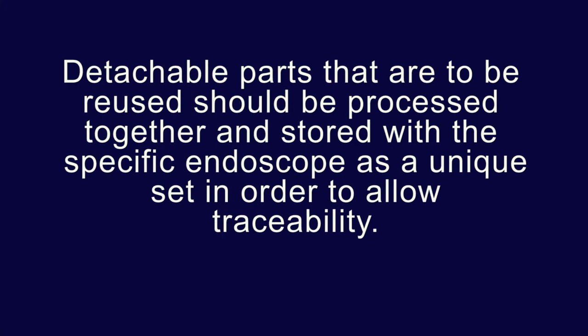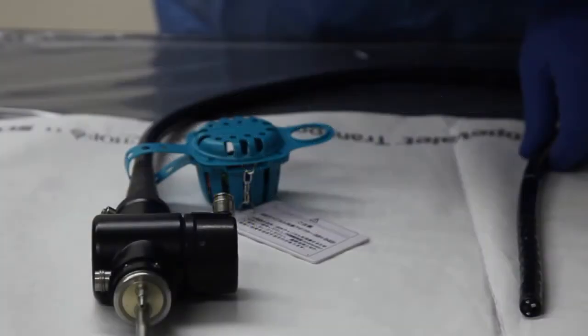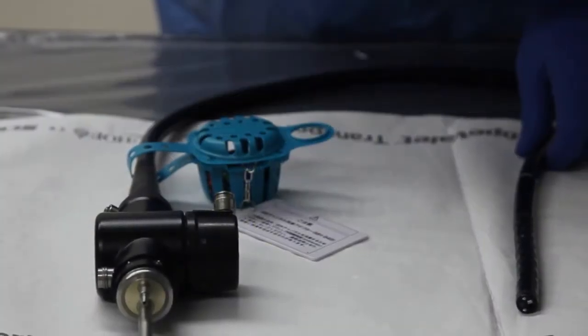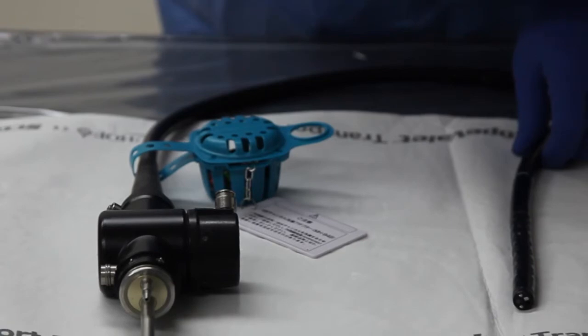These guidelines state: Detachable parts that are to be reused, for example, air, water and suction valves and pistons, should be processed together and stored with the specific endoscope as a unique set in order to allow traceability. To keep the parts together with the scope, a small bag or similar device can be used to attach the parts to the scope.